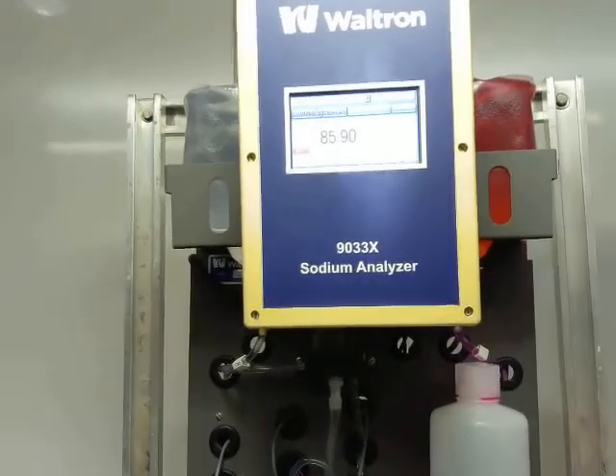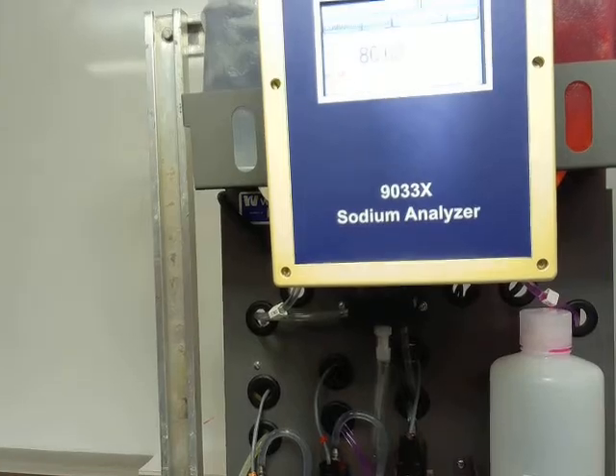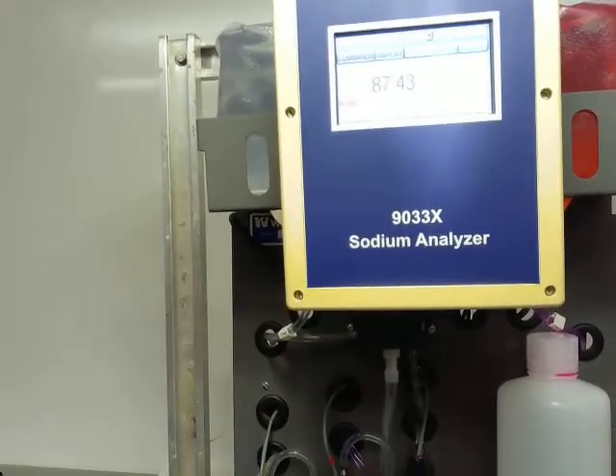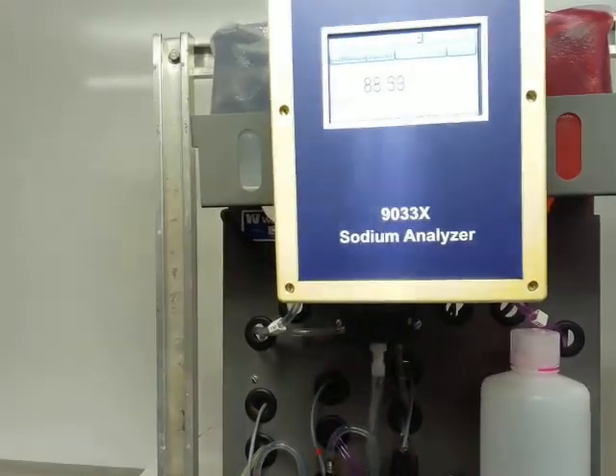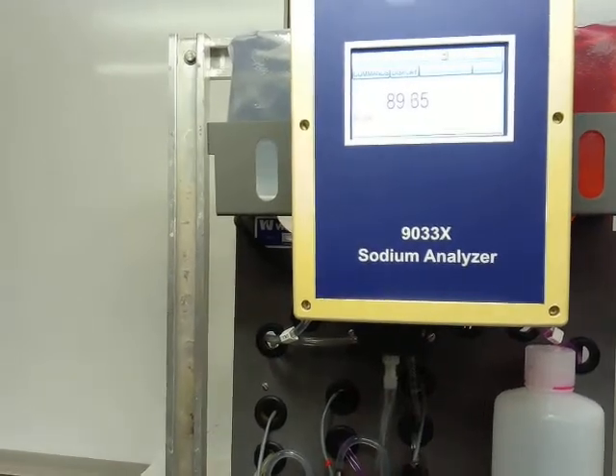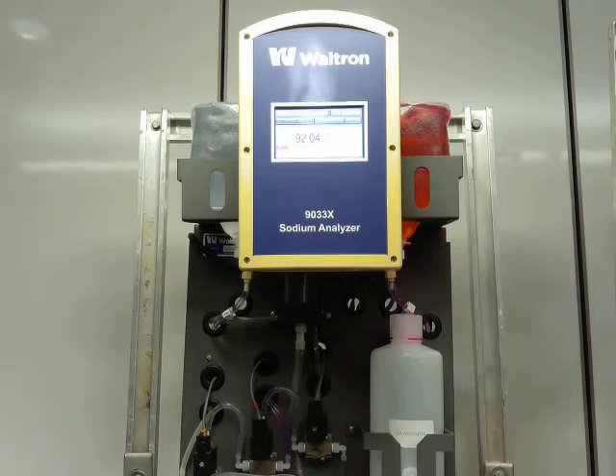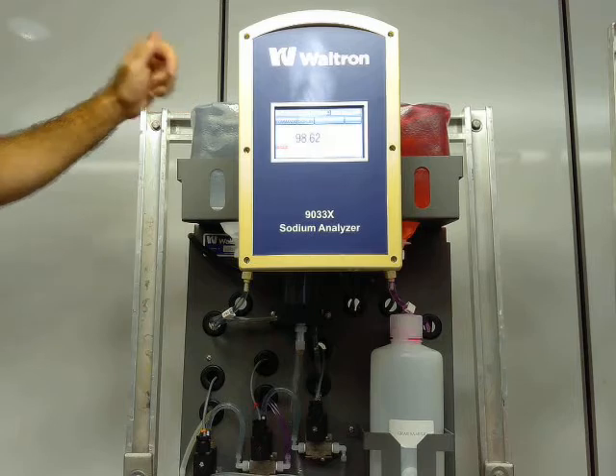What we can see now is that I started the calibration, our first valve opened up, and the screen during calibration will show about what reading it thinks it is. It's reading about 89 right now. Depending on the last cal, that may or may not be close to 100. If your last cal was a long time ago or it's getting started for the first time, that number could certainly be wildly different from 100. What's important to note is that when it does...